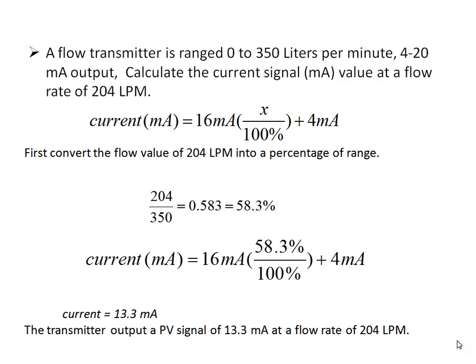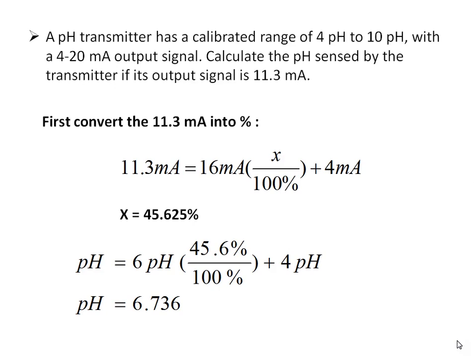Here, X is the process variable. So the transmitter outputs a process variable signal of 13.3 mA at a flow rate of 204 lpm. In another example, a pH transmitter has a calibrated range of 4 to 10 pH with a 4 to 20 mA output signal. Calculate the pH sensed by the transmitter if the output signal is 11.3 mA. This is the reverse of the earlier example — here we know the output current and need to find the pH. Converting 11.3 mA into a percentage gives approximately 45.625%, corresponding to 11.3 mA. Placing this in the equation, we get a pH of approximately 6.736.